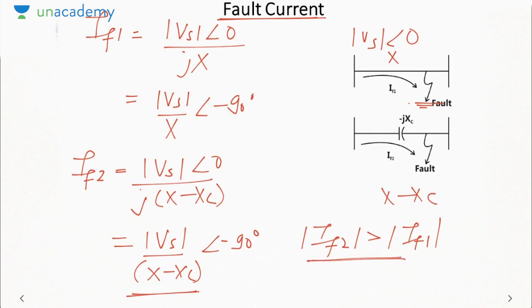Now what is the ill effect of an increase in fault current? First of all, since the fault current will increase, the heating in the system will increase, which can damage the system. Secondly, whatever protection system I design will have to be of a higher rating because the fault current increases. Usually whenever a fault comes, the circuit breaker has the role to separate the plates of the circuit breaker and open the circuit.